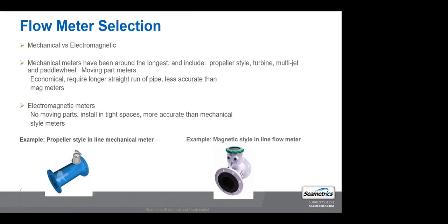As electromagnetic meters have become more and more common, the demand of them has gone up, the price of them has come down. Mechanical meters require a longer straight run of pipe than mag meters do, and I'll get into that in just a few minutes on what that means. And mag meters have no moving parts. They install in a real small footprint. So if it's an old well and now you need to put a meter there and you don't have a lot of straight run pipe, mag meters are a good choice for that.